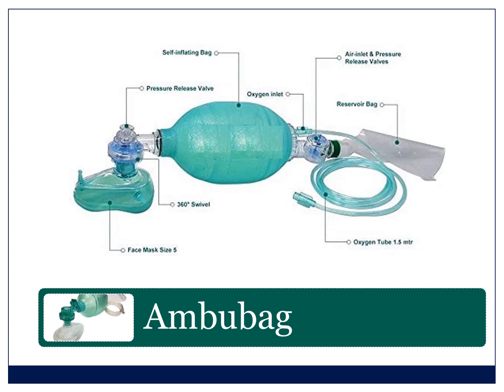It's hard to ventilate if your machine dies. Check that you have an ambu bag, check that it works. This is an ambu bag. What I suggest you do is you take it out of that packet that it hangs on at the back of the machine. You take off the face mask and you occlude the end of the ambu bag, and then you just press your self-inflating bag. And you should be able to generate a pressure in that bag. That's all you need to do. Stick it back in the bag behind the machine. And now if your machine dies, at least you can ventilate the patient. You'll be able to suction, ventilate the patient, and you've got an oxygen cylinder if you run out of oxygen during the case.